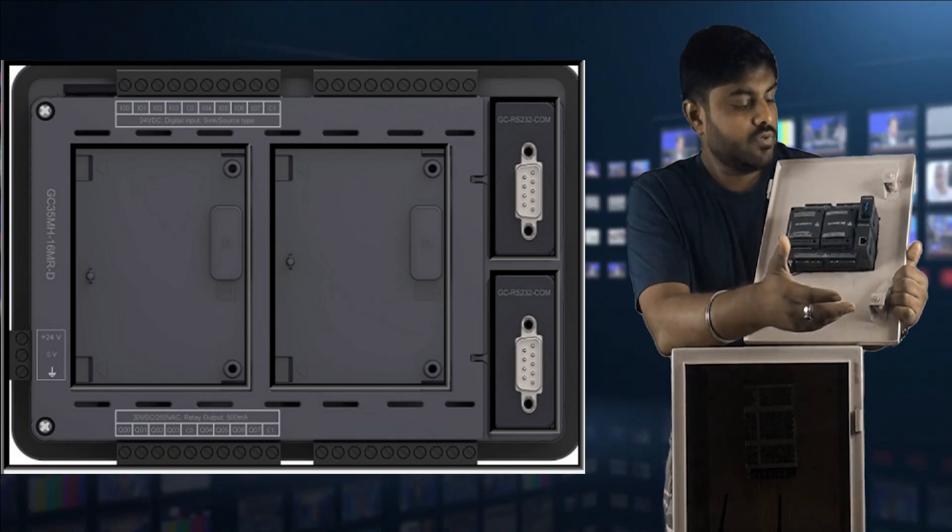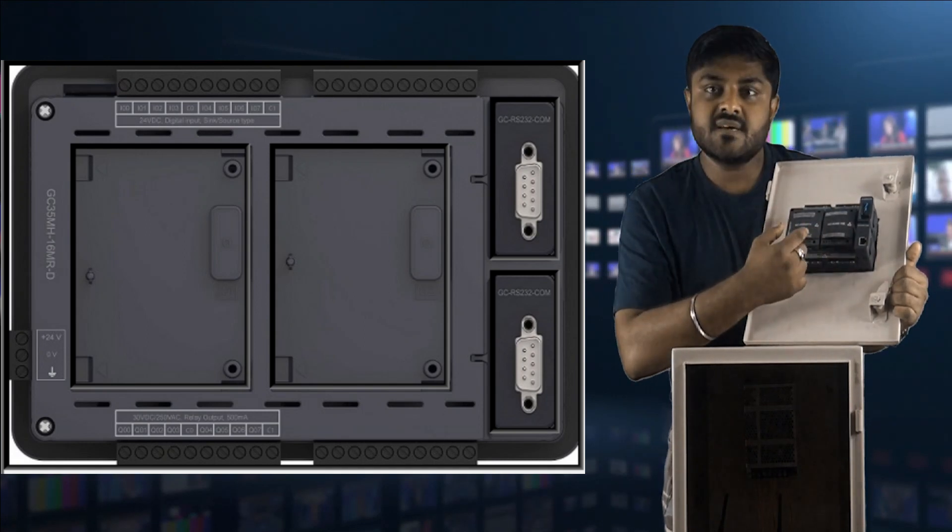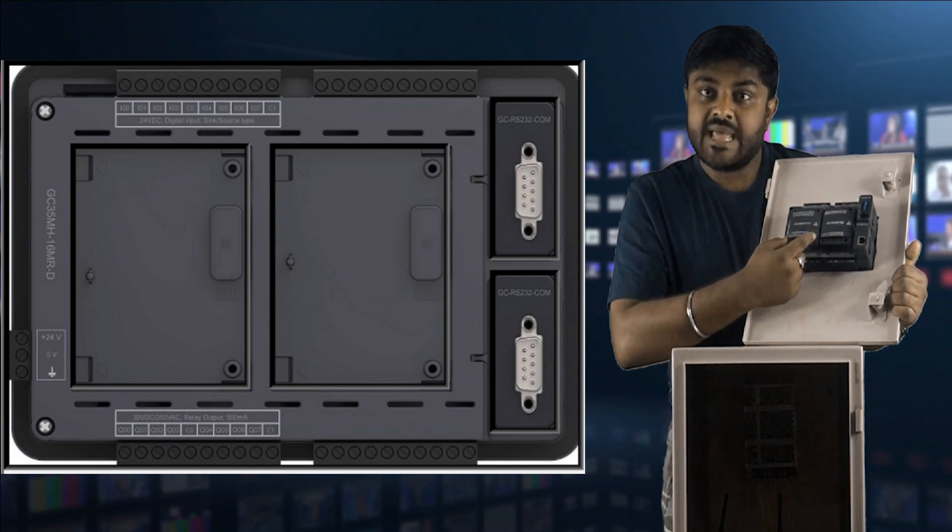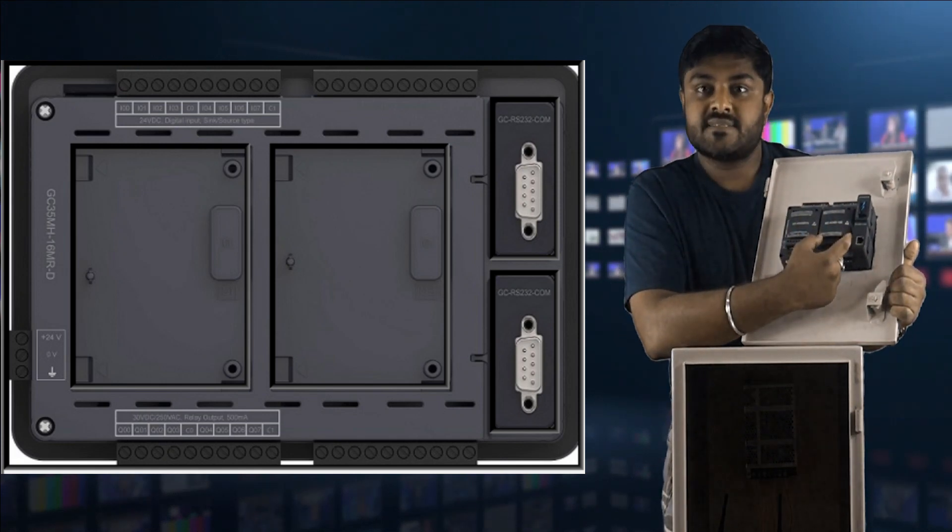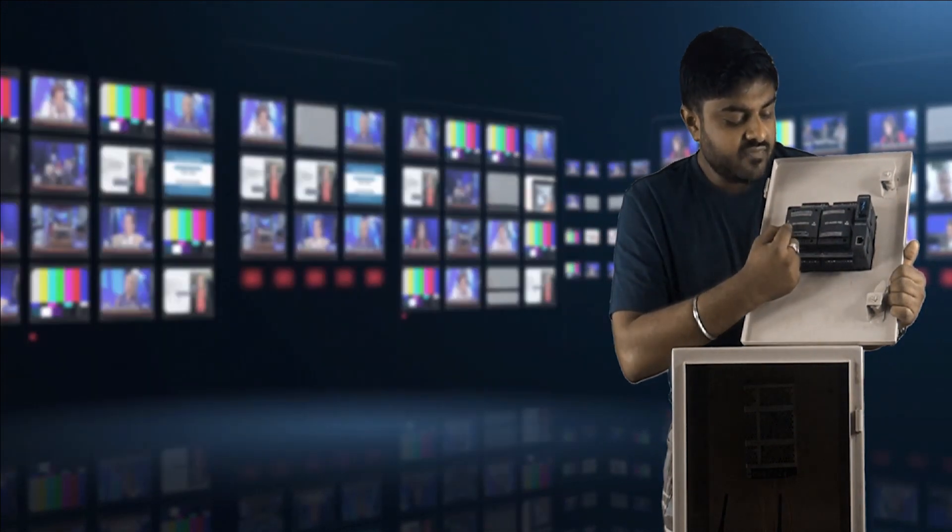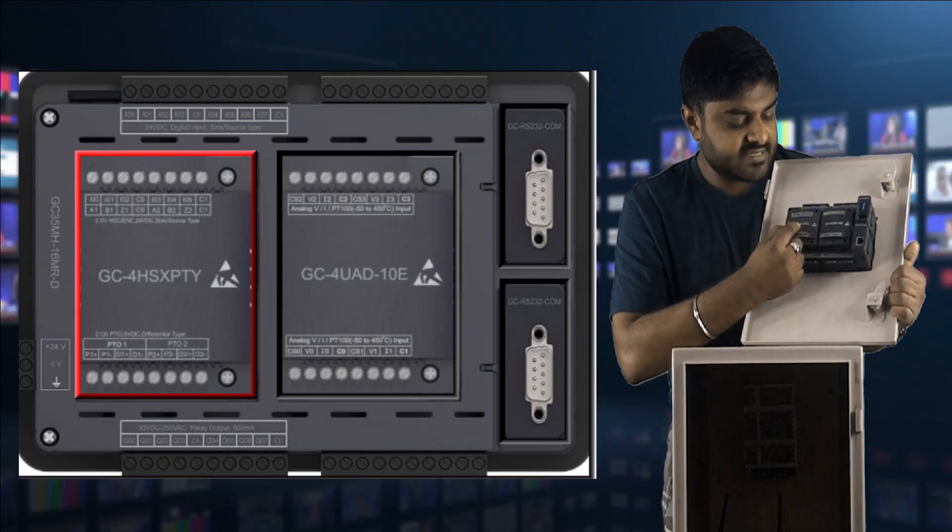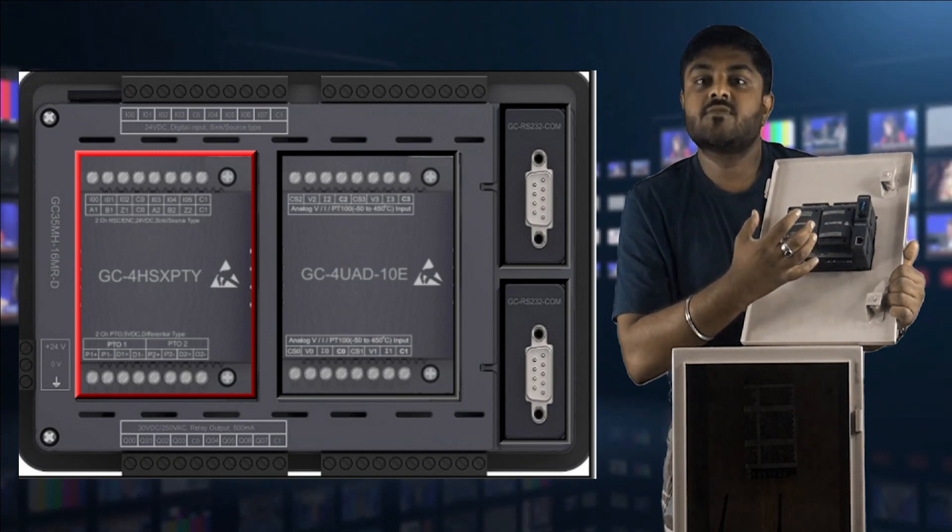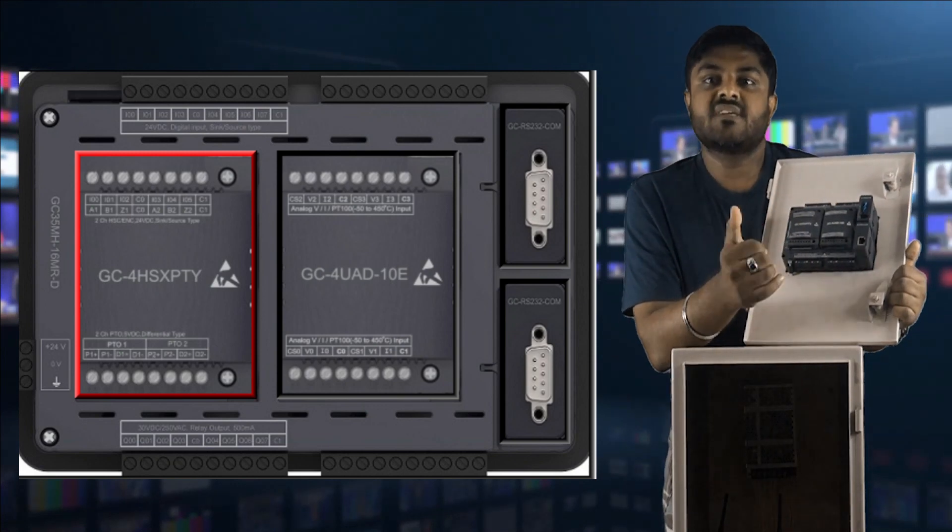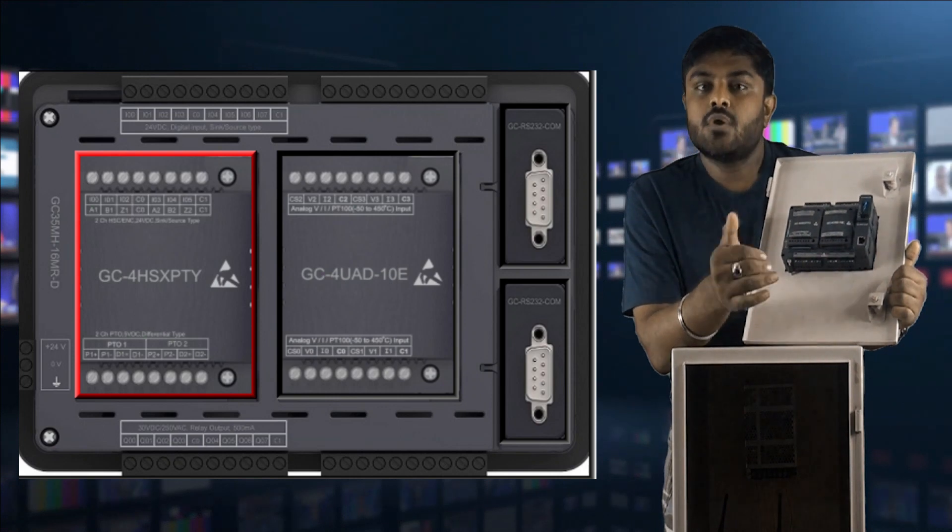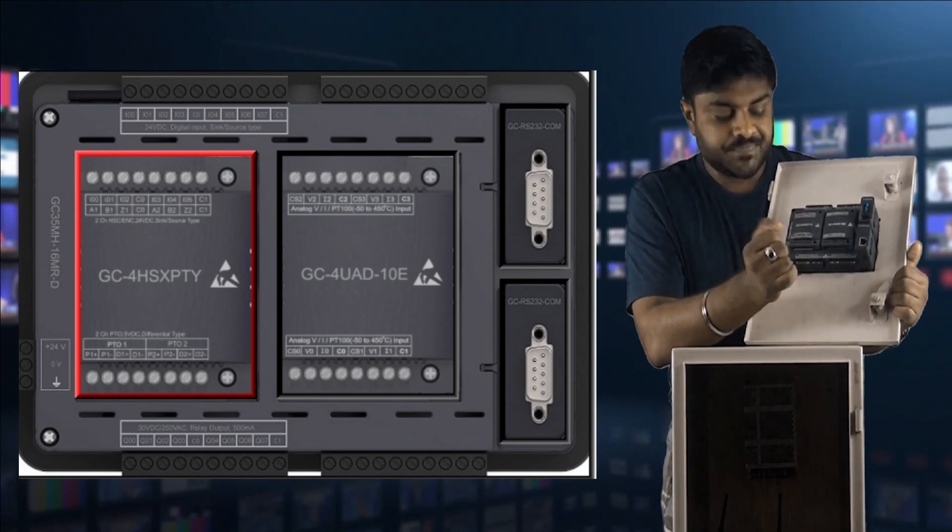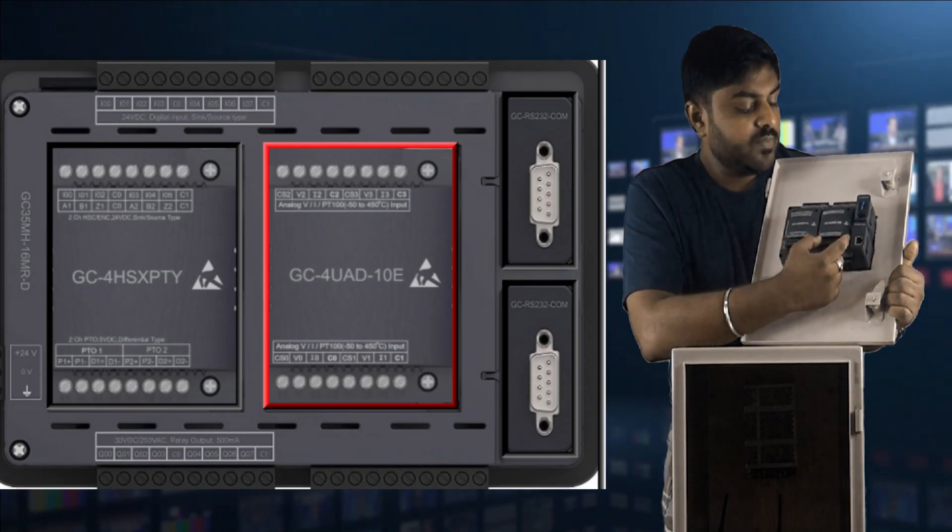Here you can see another two attachments over here. This is one extension module slot, and this is another extension module slot. In first module slot, we interface GC-4HSXPTY. It is a high-speed input module, and it will give pulse output to particular drives or particular controller to run servo as well as stepper motor.